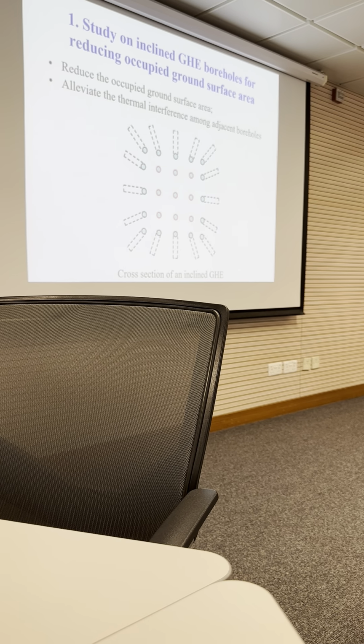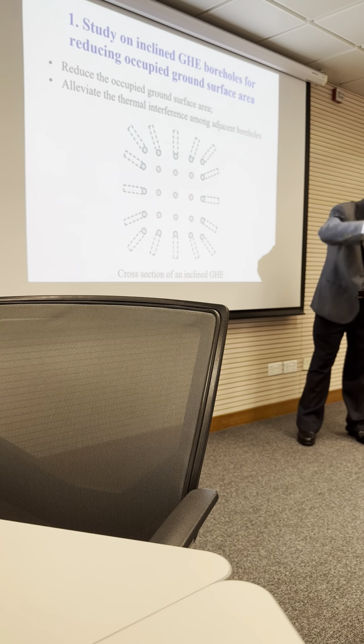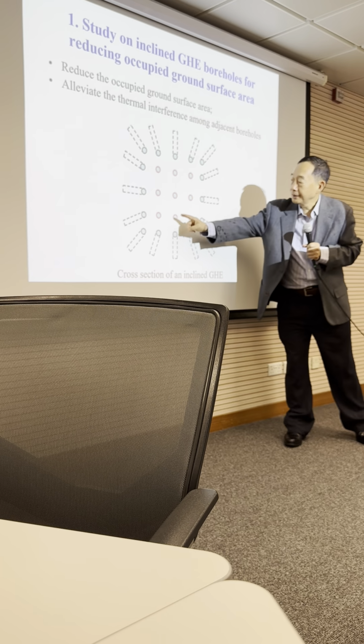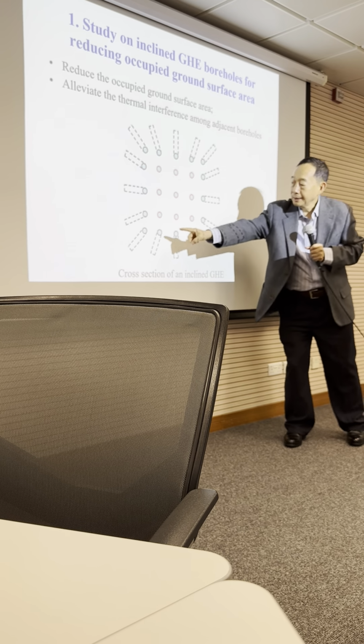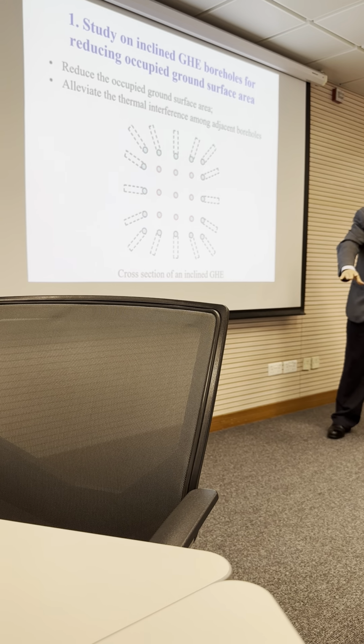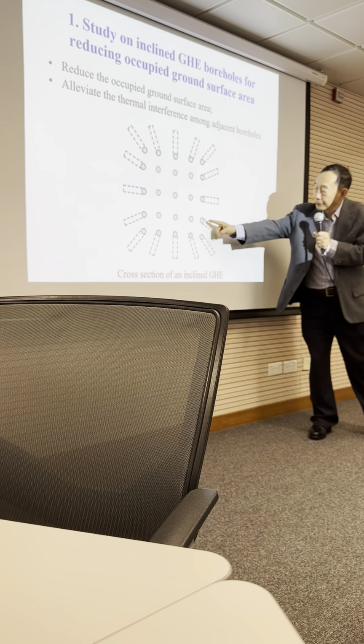You see, we know in Hong Kong we have to inject a lot of energy into the ground. Then we need to drill boreholes. If the boreholes are all exactly vertical, then the underground area is limited. But if we can drill inclined boreholes, inclined to the outside, then the underground space is much larger. So we can partially solve the unbalanced problem of injecting energy into a large space.